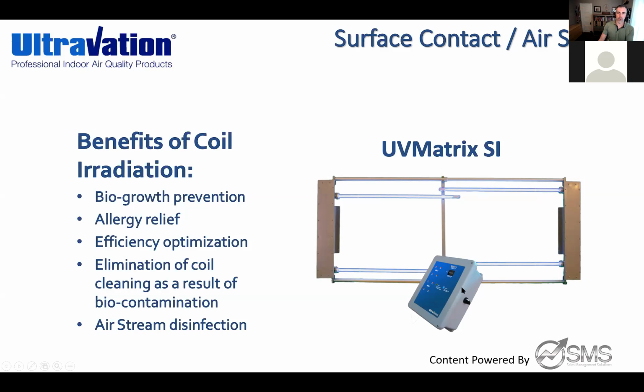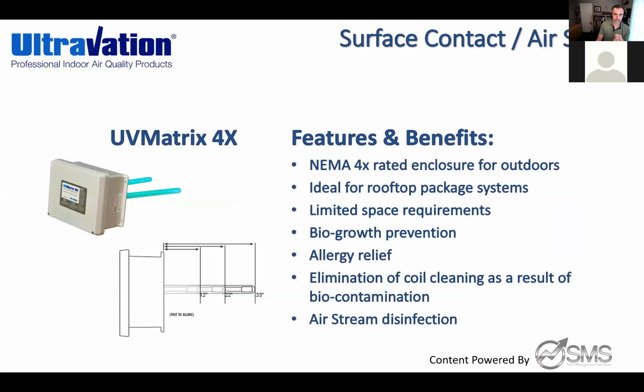Some people want remote monitoring so they can see by those little lights on the box that all the lights are lit up. Other people don't pay for that. We even sell sight glasses where you can cut into the access door and put a sight glass in that doesn't let the UV light come up. You can look through the door and see everything lit up. We even have remote monitoring modules that actually monitor light intensity.